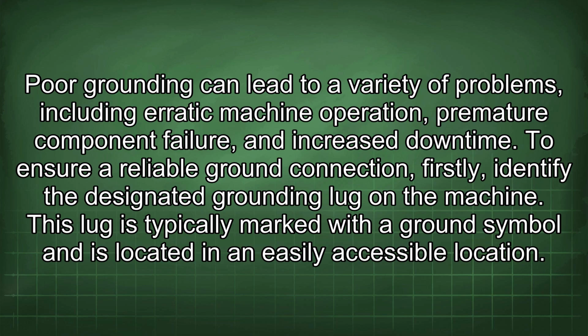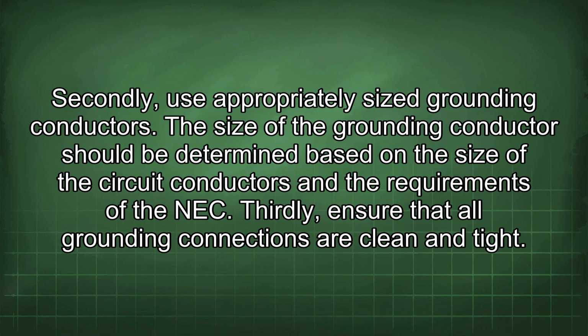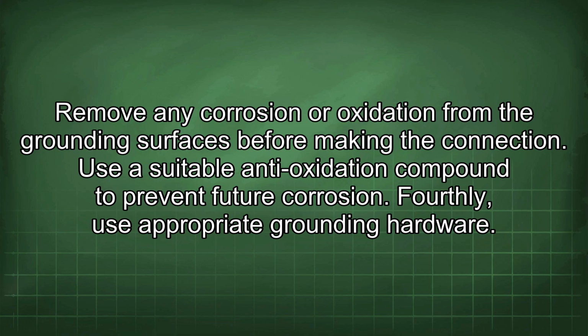downtime. To ensure a reliable ground connection, firstly, identify the designated grounding lug on the machine. This lug is typically marked with a ground symbol and is located in an easily accessible location. Secondly, use appropriately sized grounding conductors. The size of the grounding conductor should be determined based on the size of the circuit conductors and the requirements of the NEC. Thirdly, ensure that all grounding connections are clean and tight. Remove any corrosion or oxidation from the grounding surfaces before making the connection. Use a suitable anti-oxidation compound to prevent future corrosion.